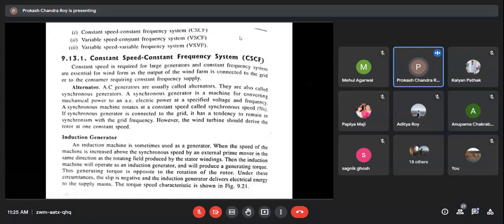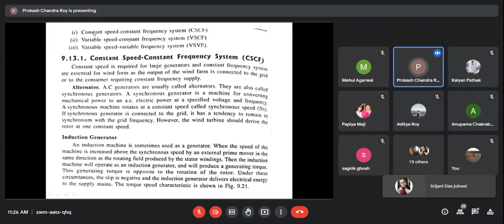Here you have the constant speed and constant frequency system — mostly we want this type of system. Depending upon the speed of the shaft or rotor, your frequency is fixed; for India it is 50 Hz. Depending on that, the number of poles of the generator will vary. If you have a four-pole machine, the speed should be 1500 rpm; if you have an eight-pole generator, it would be 750 rpm. That is the constant speed, constant frequency system.